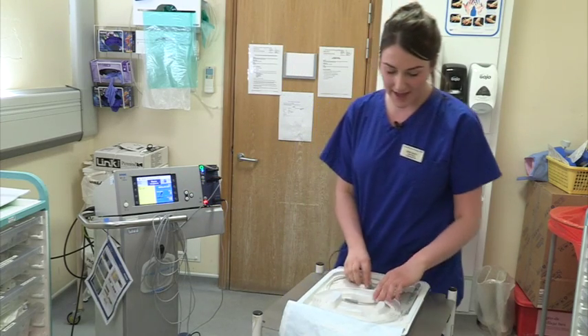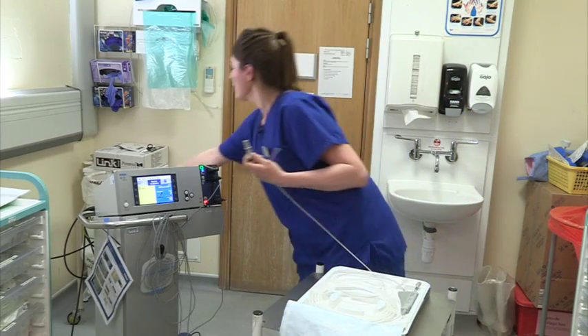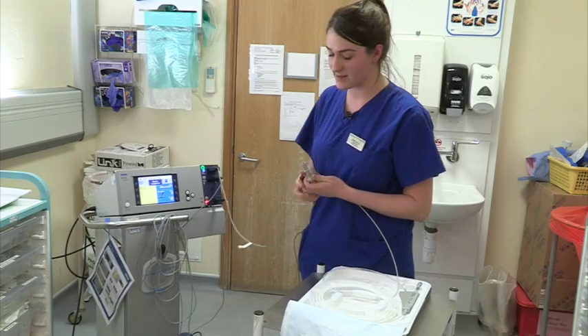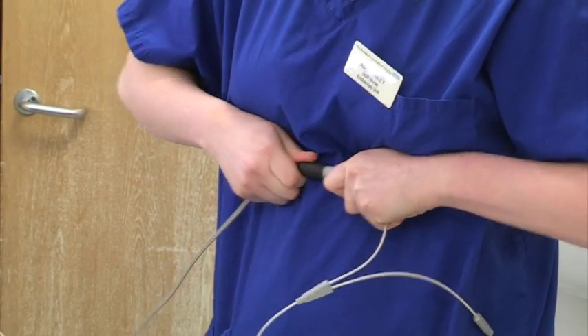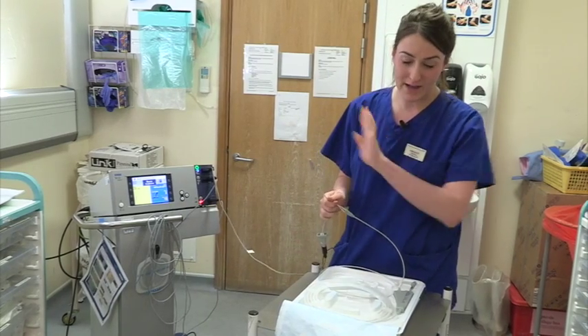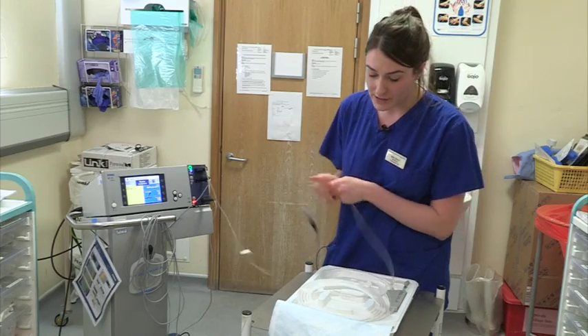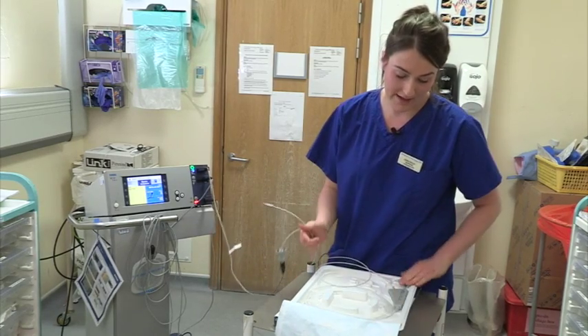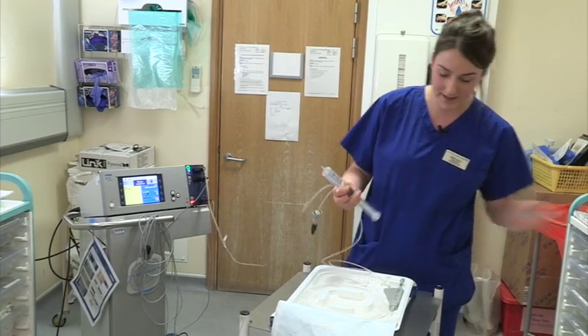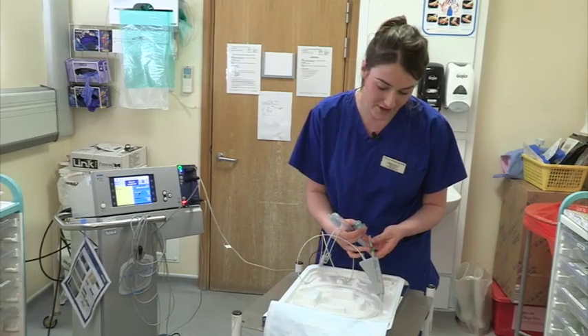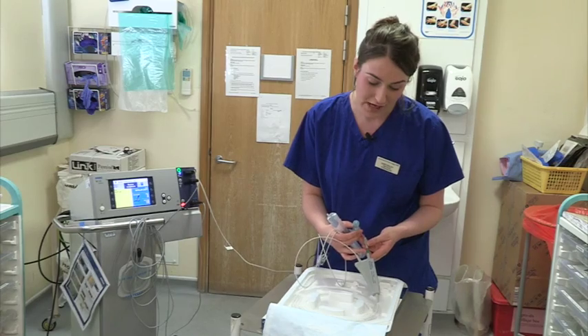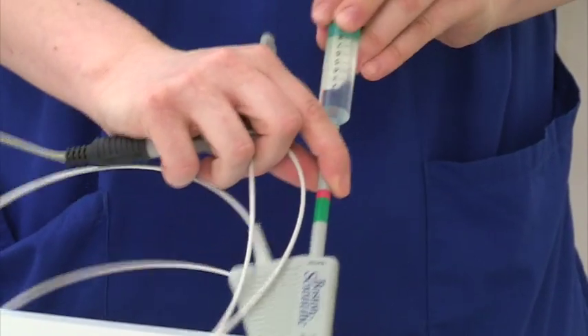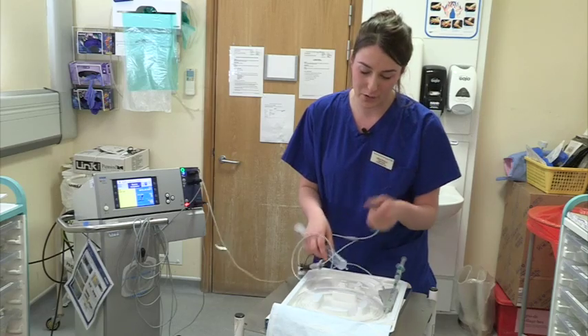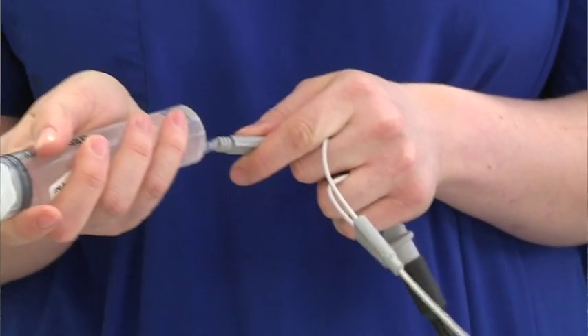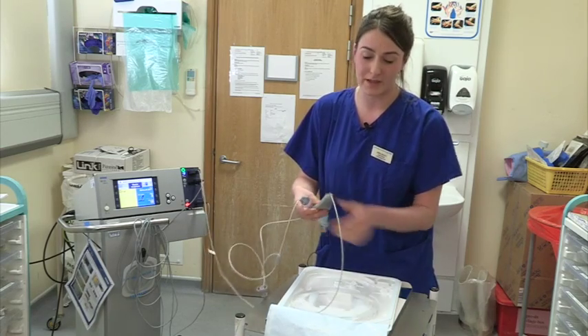Once you've done that, then you can connect your gold probe with the connector to the machine. So this connects to the bipolar section and it just literally pushes in. So that is now connected. Then you need to make sure everything's ready to be used before you hand it to the doctor. What I would suggest is to leave the sheath on and connect your syringes first. So you have your saline and your adrenaline. Adrenaline connects to the injection hub. On the injection hub we have the red and green sections. Just think of these as safe zones and danger zones, which I shall go through when I talk through injection. So adrenaline on there. Irrigation port is where the saline will go. Connect your saline, and then I would suggest that you hold these both together, as these are what you'll be using. Then you need to unsheath the gold probe to hand to the doctor.